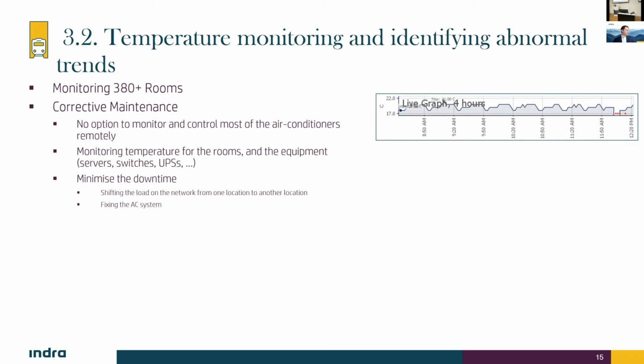The first thing is, for example, you have an air conditioner in the room, so you need to deal with reality. The problem is that most of those air conditioners don't have any remote monitoring or control feature. They're simple air conditioners, and anyone can go inside the room. For example, a technician working inside feels it's a bit cold, so they change the temperature. After 2 hours, you see the temperature going high in the room, and you get an alarm on the system saying that in 2 minutes everything goes down because it's too hot.